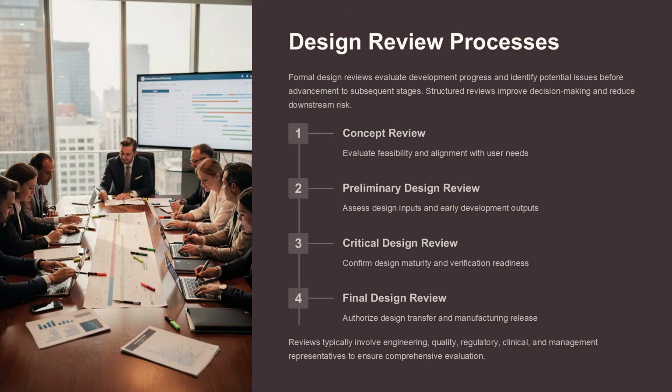Formal design reviews evaluate development progress and identify potential issues before advancement to subsequent stages. Structured reviews improve decision-making and reduce downstream risk. They involve evaluating feasibility and alignment with user needs, assessing design inputs and early development outputs, confirming design maturity and verification readiness, and authorizing design transfer and manufacturing release. Reviews typically involve engineering, quality, regulatory, clinical, and management representatives to ensure comprehensive evaluation.